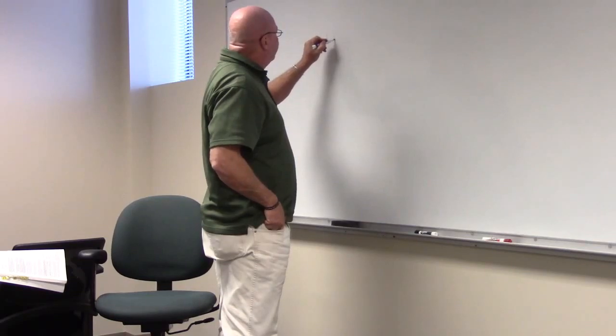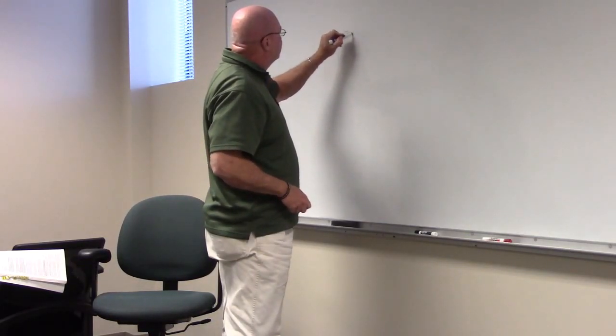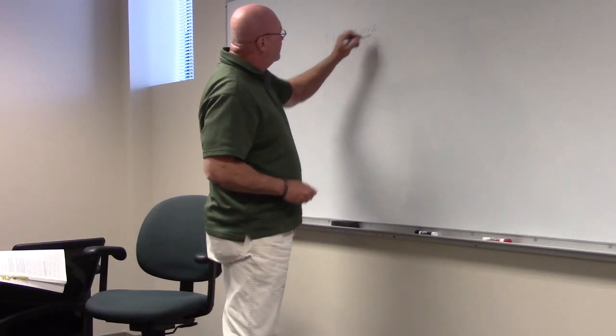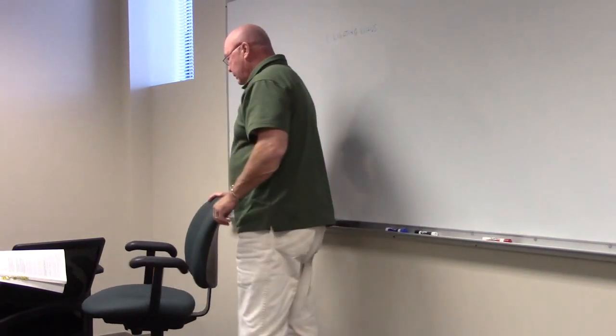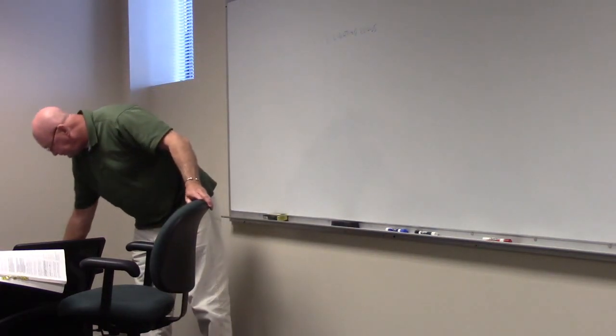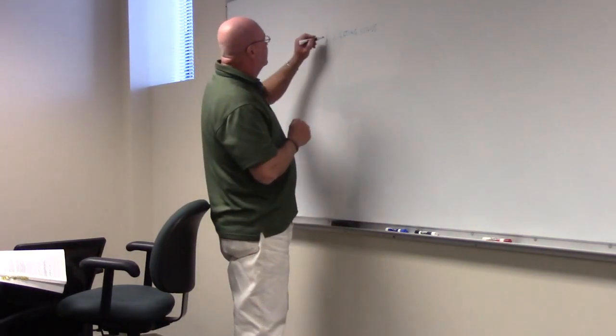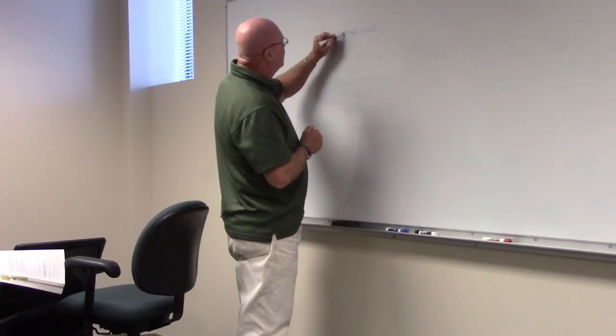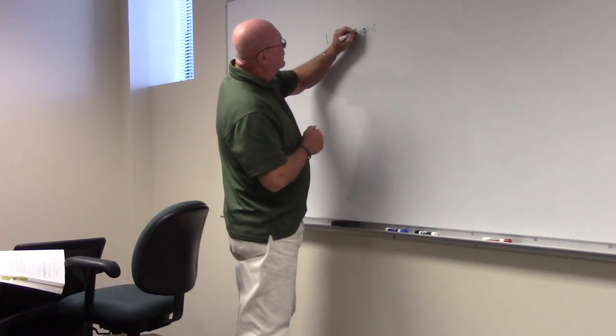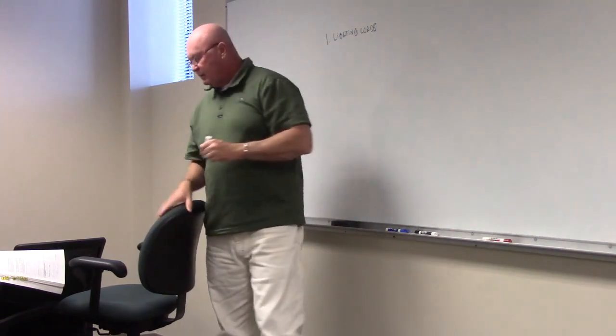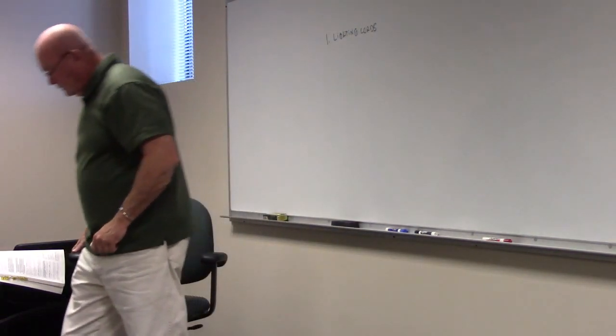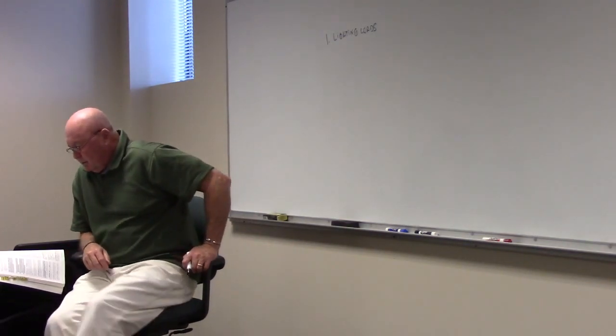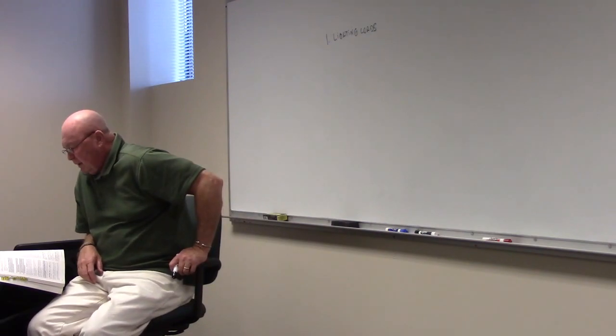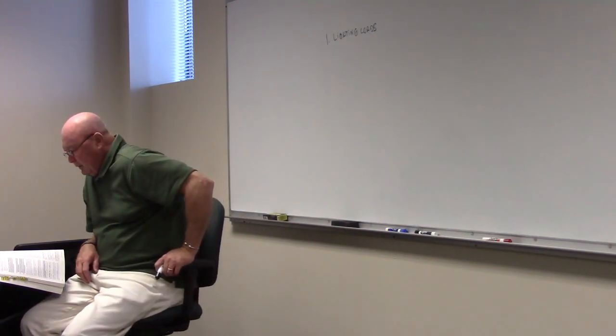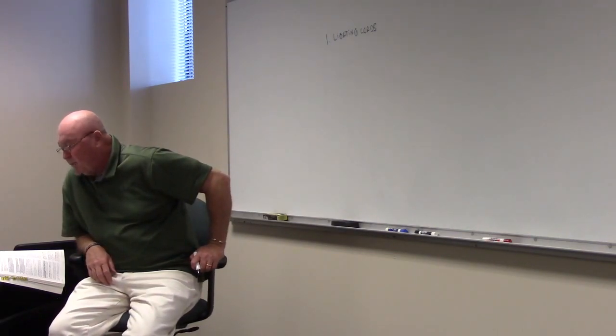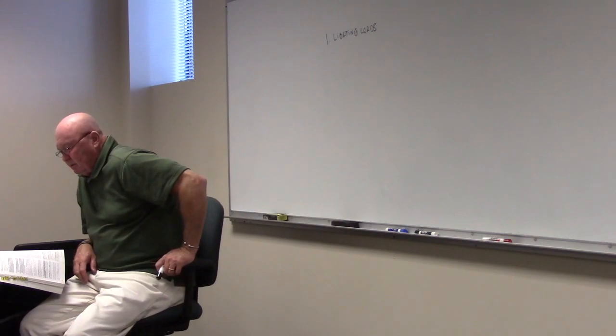So step one. Let's see if I can get a better marker. And how about that chart? See it there? You understand it? Let's say for residential, we're just gonna do a house, general lighting load by occupancy. And as far as reading that table, for dwelling units, how many volt-amps per square foot does a dwelling take up?